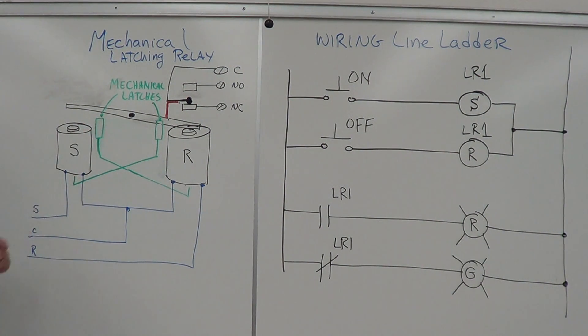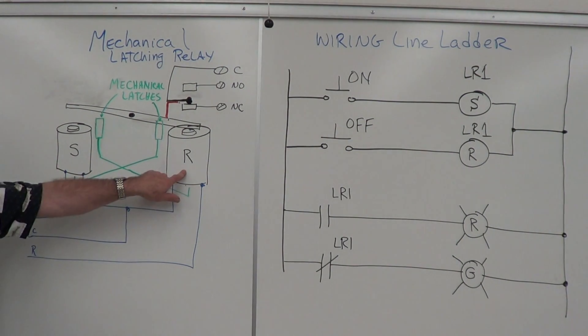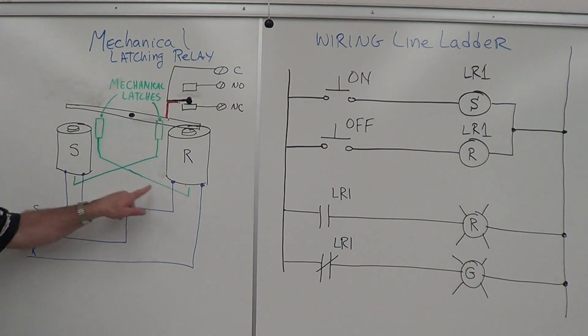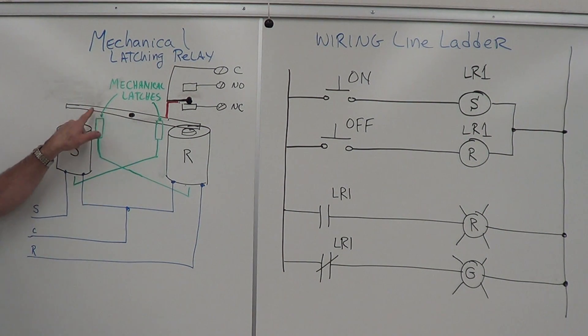Now it's on. We want to turn it off. We energize the off coil, which causes the mechanical latch to reset, pull out, release the lever, and then the bar pulls down and latches in place with its side mechanical latch. Then we can release power from the coil.